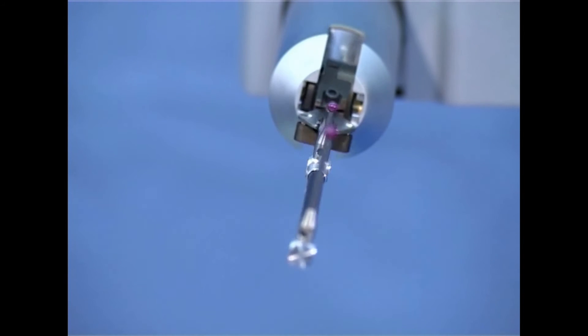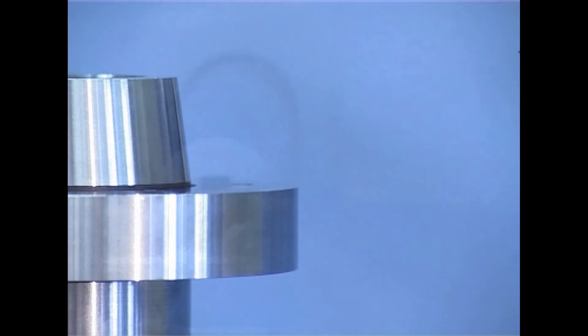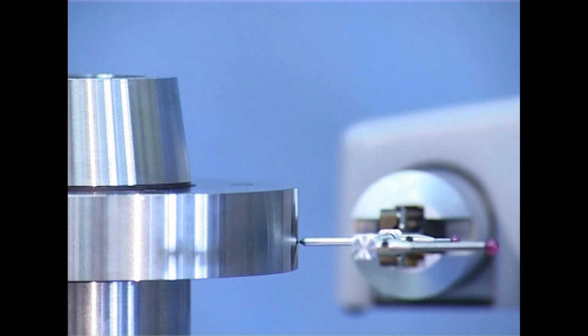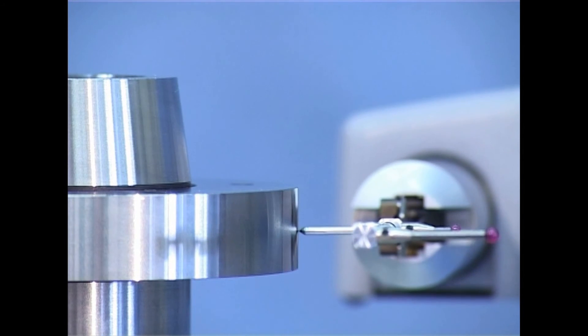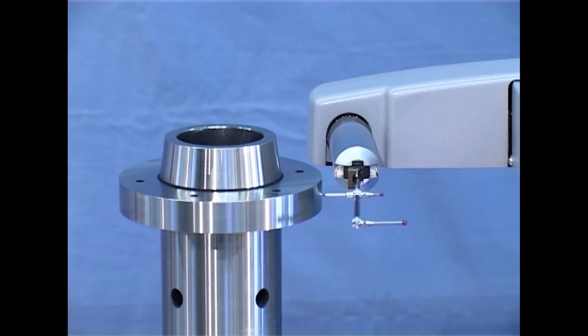Different probe tips must be used for standard form and roughness measurements. In Hommel-RoundScan, a CNC-controlled rotation and tilt module positions the ruby ball and the diamond tip anywhere on the workpiece. This is achieved by the scanning system active on both sides in connection with the 270 degrees rotation possibility of the tilt module.